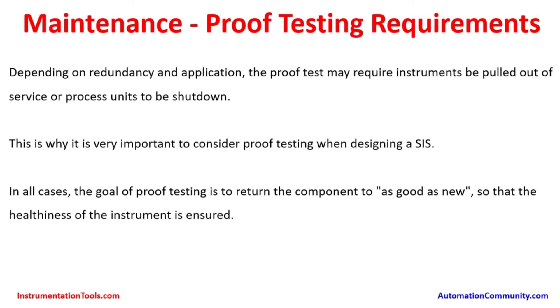Depending on the redundancy and application, the proof test may require instruments to be pulled out of service or the process needs to be shut down. This is why it is very important to consider proof testing when designing a SIS. In all cases, the goal of proof testing is to return the component to as-good-as-new condition so that the healthiness of the instruments is ensured — not only instrument healthiness, but also protection for people, the environment, and mechanical equipment.